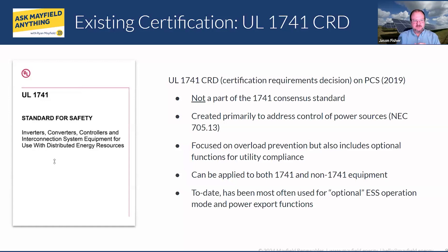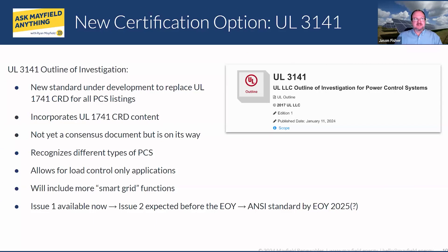Between the second and third editions of UL 1741, there were a bunch of CRDs that are now part of the official third edition, since we finally went through all that process. These are things not addressed by the NEC, so you won't find them there. You could go to an individual utility and they might agree to it, but that's not easy.